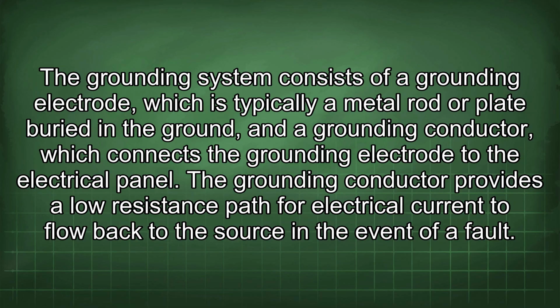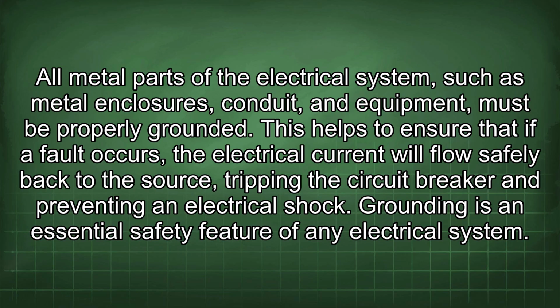The grounding conductor provides a low resistance path for electrical current to flow back to the source in the event of a fault. All metal parts of the electrical system, such as metal enclosures, conduit, and equipment, must be properly grounded. This helps to ensure that if a fault occurs, the electrical current will flow safely back to the source, tripping the circuit breaker and preventing an electrical shock. Grounding is an essential safety feature of any electrical system.